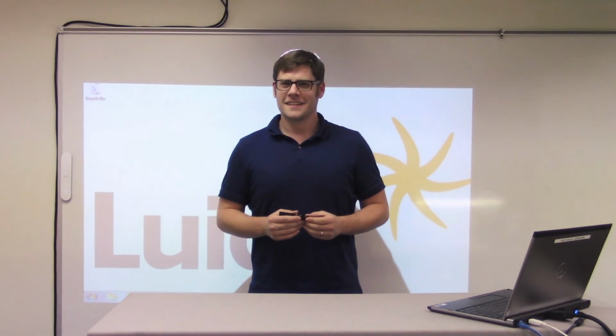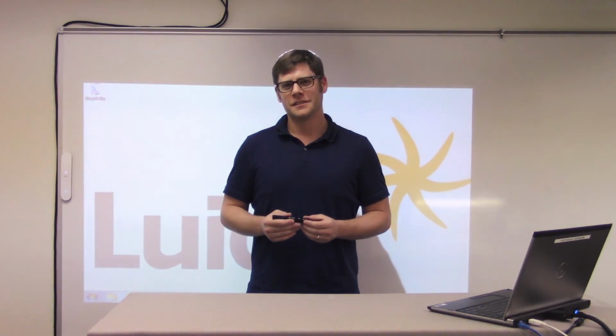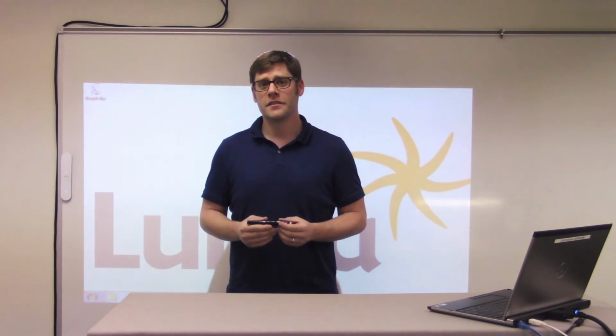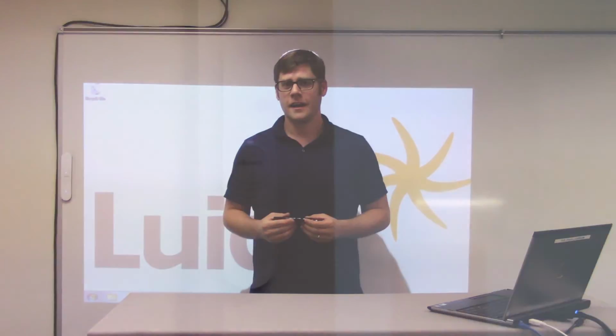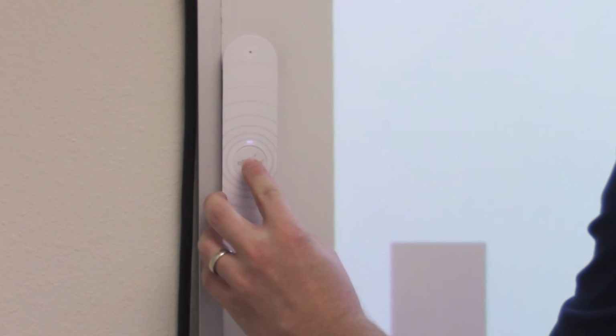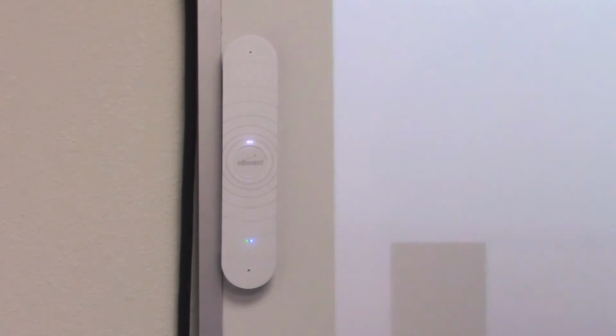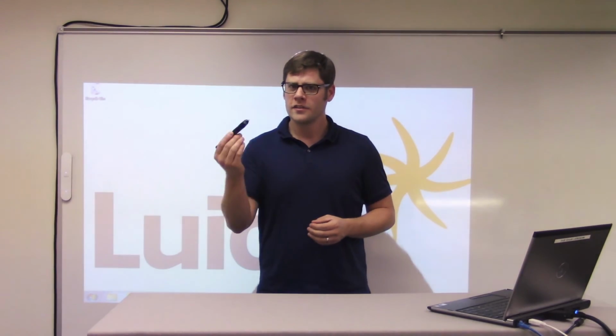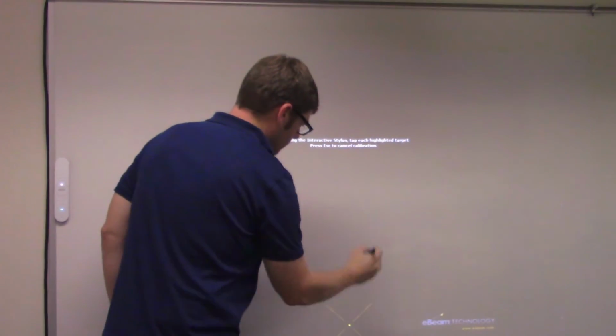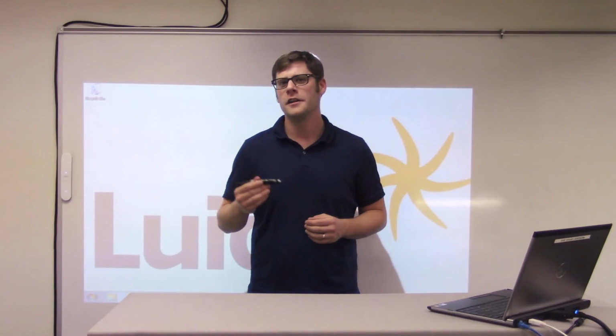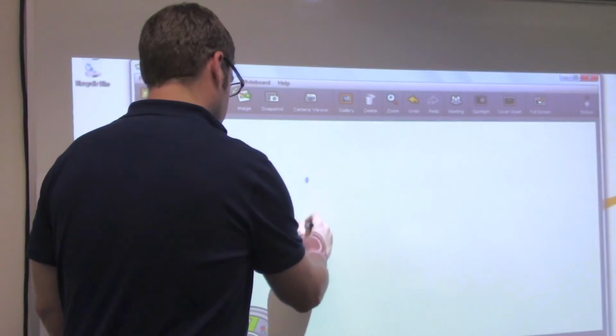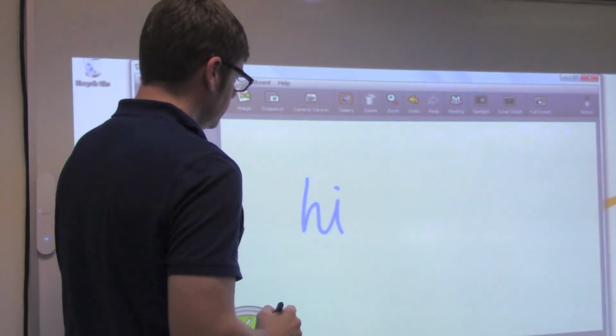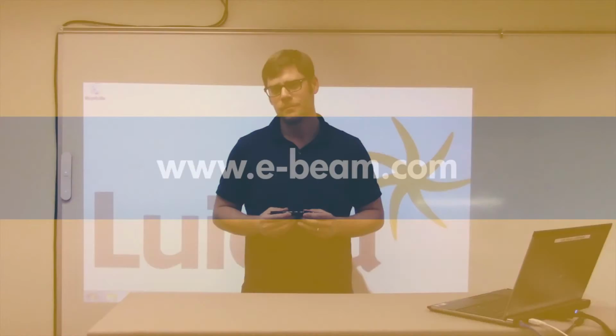After your sensor is connected and placed, the final step is calibration. So to start calibration, simply press the middle button on the sensor and the display will change to a black screen with 9 white dots on it, the top left dot having a target around it. Using the stylus, tap the dot in the middle of the target. Continue tapping each dot with the targets around it until you've tapped all 9 dots. Once you've tapped all 9 dots, the calibration screen will disappear and your Edge Plus is ready to be used.